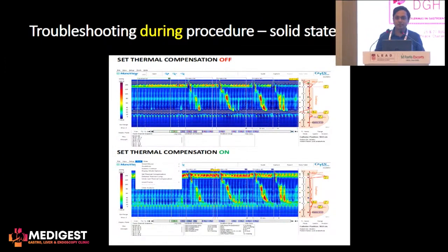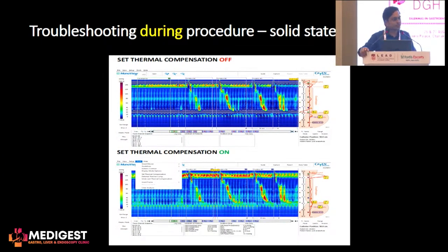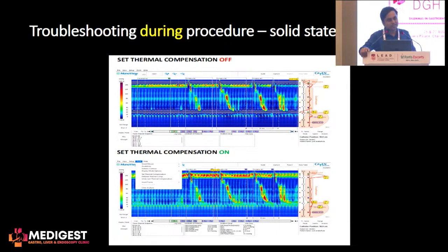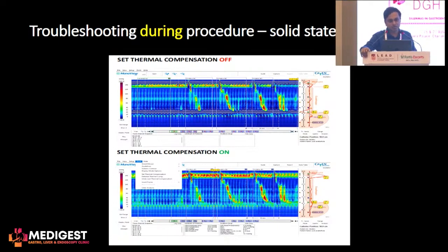With solid-state manometric catheters, though these are available at only very few centers, there is something called temperature drift. In these cases, there is an option to set thermal compensation, and you should make sure that thermal compensation is switched on when you are using a solid-state catheter.